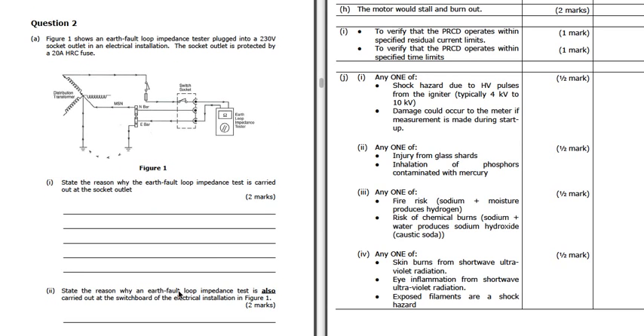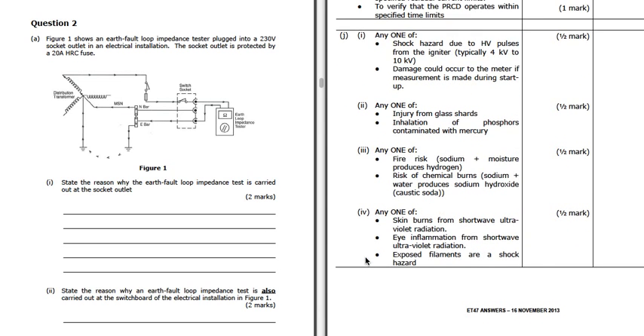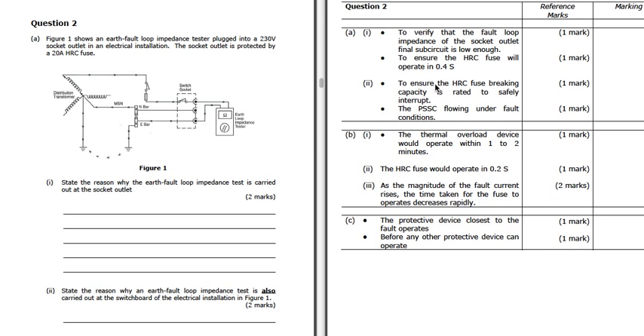Number two, we've got an earth fault loop impedance tester plugged into a 230 volt socket outlet in an electrical installation. The socket outlet is protected by a 20 amp HRC fuse, high rupturing capacity fuse. State the reason why the earth fault loop impedance test is carried out at the socket outlet. Now, when we carry out the test at the socket outlet, we're looking to verify that the fault loop impedance, so the impedance of this path and the path through the earth, we've got a parallel path, is low enough so that an HRC fuse will operate in 0.4 seconds. So we want a low enough impedance to give us enough current so that the fuse will blow quickly, in 0.4 seconds.